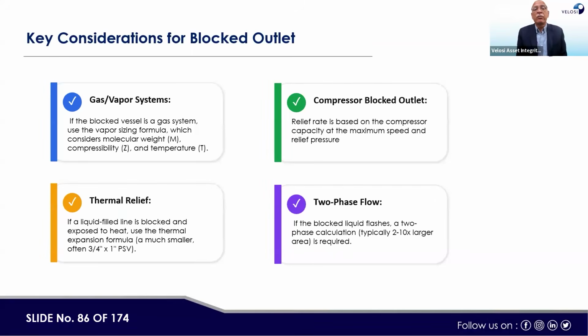Then key considerations for the blocked outlet, for example, whether it is a gas vapor system, right? This is one. Then there could be a thermal relief, compressor blocked outlet, or two-phase flow outlet. So there are various scenarios which are required to be considered. Like a gas vapor system block or thermal relief, which I gave as an example earlier. Compressor blocked outlet means the relief rate is based on the compressor capacity at the maximum speed and relief pressure. For two-phase flow, if the blocked liquid phase flashes, a two-phase calculation is needed, typically 2 into 10 multiplied by the larger area is required generally. So this is how the outlet block capacity is being estimated.